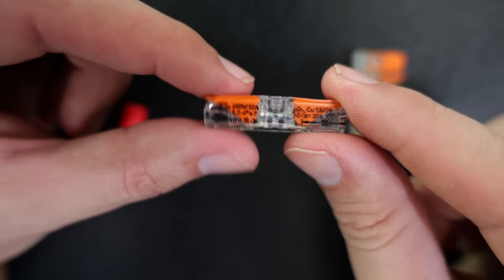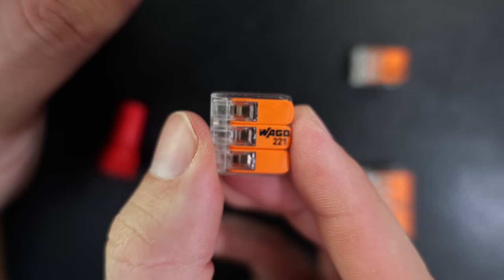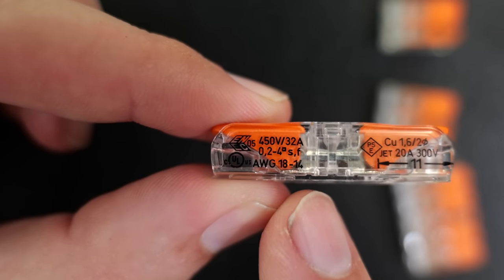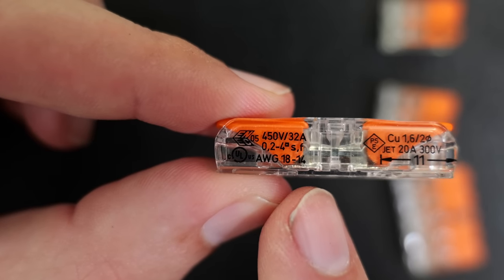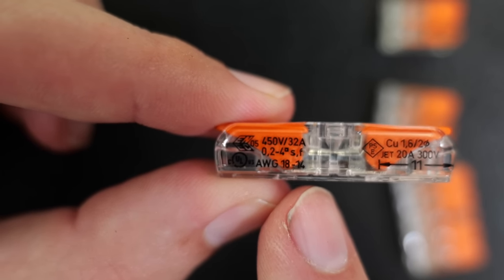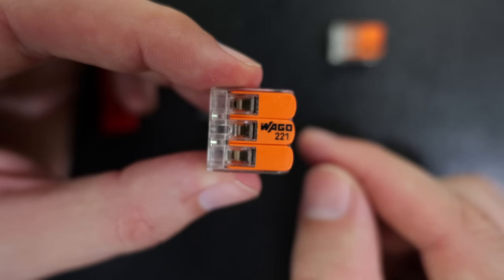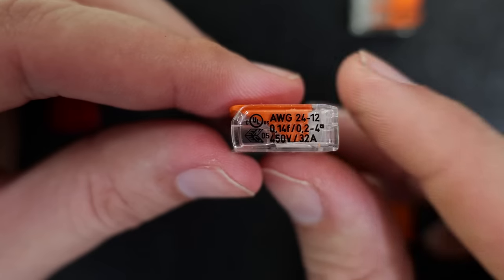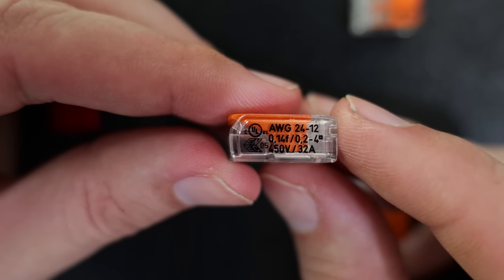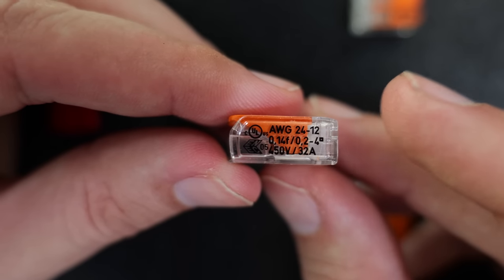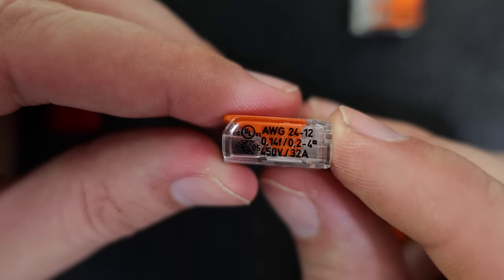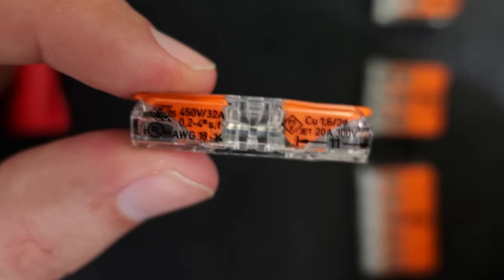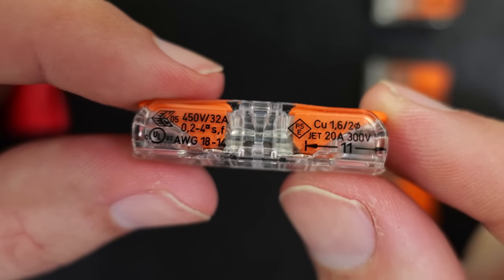Now, another area where these do differ from the original WAGO 221 connectors. If we flip the inline connector over to the side, we will see here where it says that this is capable of handling 18 to 14 gauge wire. Whereas if we look at the side of one of these original WAGO 221 connectors, we will see it says it is capable of handling wires of 24 gauge all the way up to 12 gauge. Apart from that, they're pretty much identical in what they can handle. It's really just the wiring size where they differ.